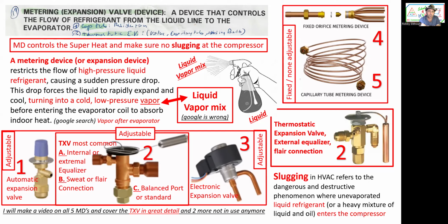Also, number 2, the picture there, is a thermostatic expansion valve with external equalizer and flare connection. You can see the picture is a little different. Number 3 is the electronic expansion valve, similar to the thermostatic, but it works electronically. And 4 and 5 are the fixed orifice and the capillary tube, which are non-adjustable. I will make a video on all 5 metering devices and cover the thermostatic expansion valve in great detail. This video is just about all the major components, all the parts of the refrigeration system. We also have 2 more not in use anymore, but it's not bad to cover them a little bit.